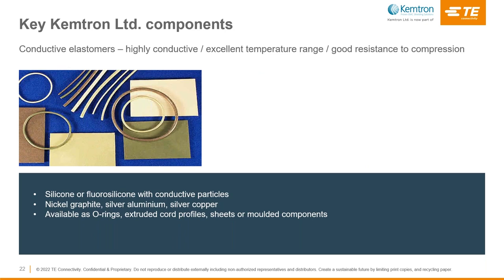Electrically conductive elastomers offer excellent shielding and environmental sealing, available in a range of materials and profiles. Nickel-coated graphite loaded in silicone, fluorosilicone, and flame-retardant UL94-V0 silicone offers economical shielding performance with good corrosion resistance. Silver-coated aluminium in silicone or fluorosilicone provides excellent shielding performance and corrosion resistance, particularly when used with aluminium surfaces, and is relatively lightweight. Silver-coated copper in silicone or fluorosilicone provides superior shielding performance with extremely low volume resistivity. Fluorosilicone offers additional benefits of chemical, fuel, and oil resistance over standard silicone. The materials can be extruded in continuous lengths in many different profiles and can also be moulded as sheet and die cut or moulded as a component.